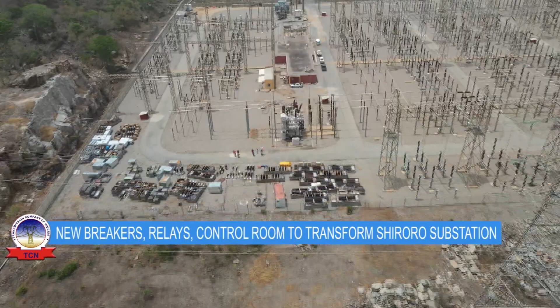In the control room of the 330/132 kV Shiroro transmission substation, which is also a sub-region, the General Manager Transmission, Shiroro Regional Headquarters of TCN, Engineer Bala Musa, explained the various components of the control room. We are in the 132 kV control room, that's the Shiroro control room. As you can see, we have the mimic board where we control and also see the status of the circuit element, that is the circuit breaker and also the isolators.